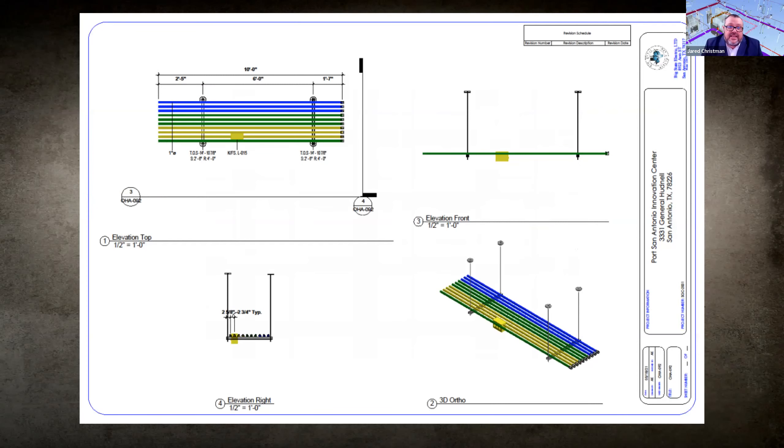On this next image you'll see an example of the rack assemblies themselves, utilizing that standardized spacing I was talking about during the video. All of these conduits are spaced exactly the same — we were able to use a gapping jig so we didn't have to measure from center of conduit to center of conduit. We also had standardized lengths between the Unistrut. The standardization is key for prefab because the more standardized your processes are, the less thought goes into those very mundane aspects — your strut spacing and conduit rack spacing.